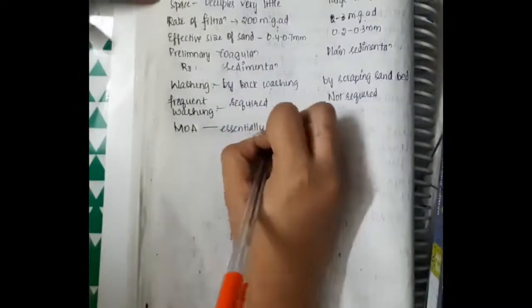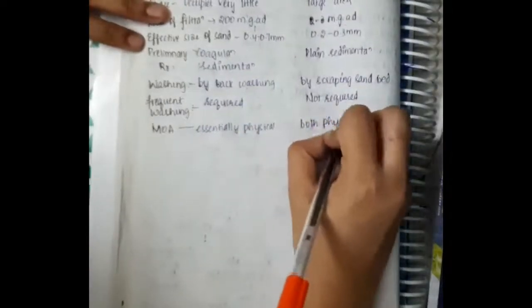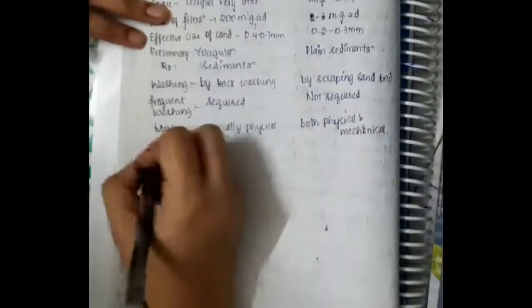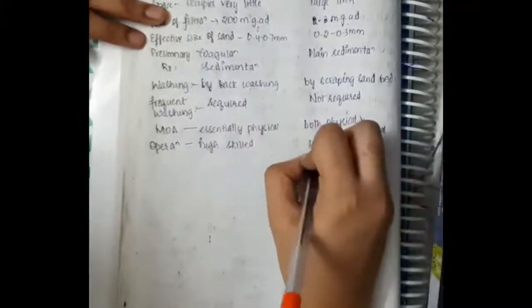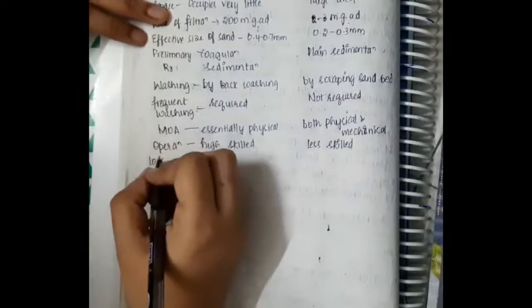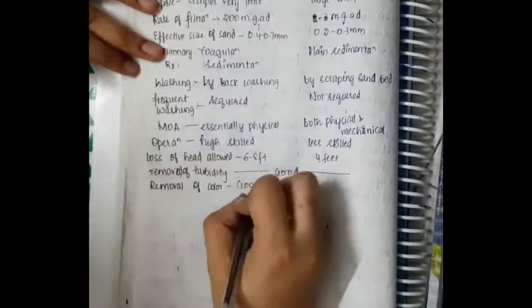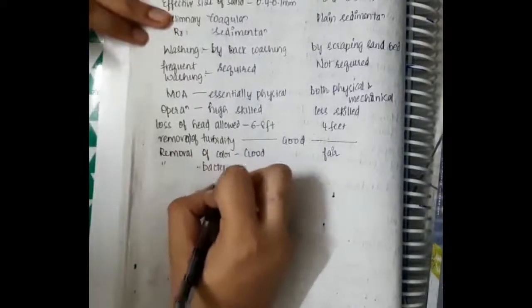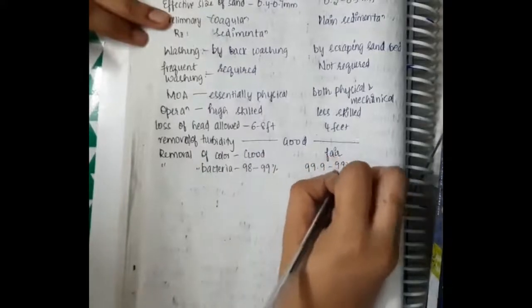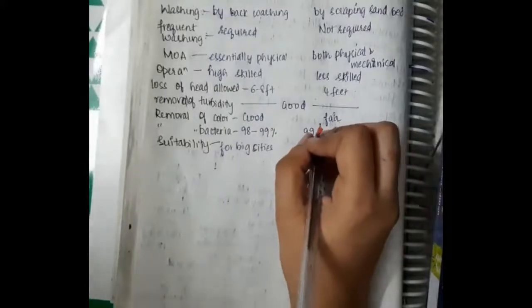The mechanism of action of rapid sand filter is mainly by physical means, whereas the mechanism of action of slow sand filter is by both physical and biological means. Operation of rapid sand filter requires high skill and that of slow sand filter is less skilled. Loss of head allowed is 6 to 8 feet in rapid sand filter and 4 feet in slow sand filter. Removal of turbidity is good for both. Removal of color is good for rapid sand filter and fair in slow sand filter. Removal of bacteria is 98 to 99% in rapid sand filter and 99.9 to 99.99% in slow sand filter. Rapid sand filters are suitable for big cities and slow sand filters for smaller towns.